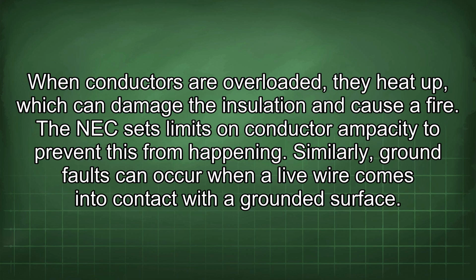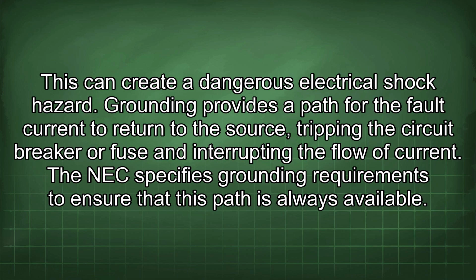Similarly, ground faults can occur when a live wire comes into contact with a grounded surface. This can create a dangerous electrical shock hazard. Grounding provides a path for the fault current to return to the source, tripping the circuit breaker or fuse and interrupting the flow of current. The NEC specifies grounding requirements to ensure that this path is always available.